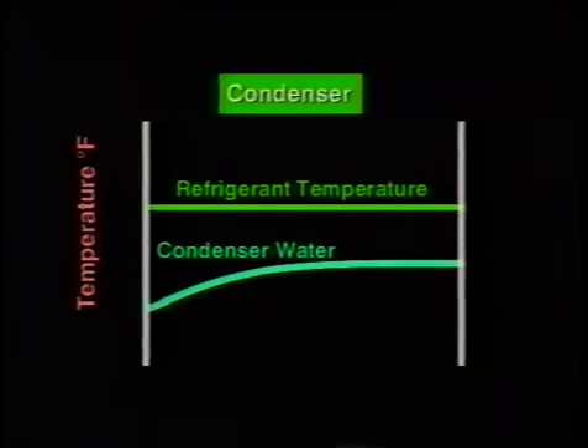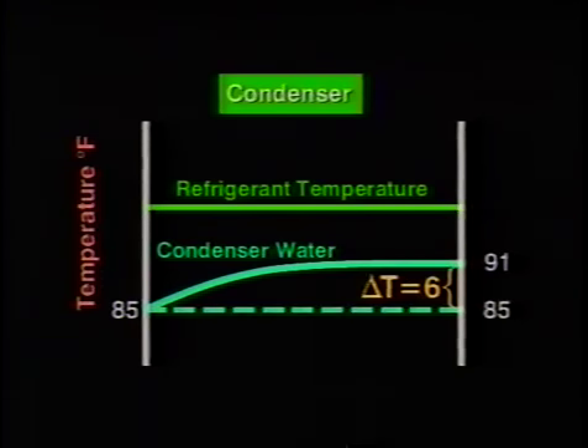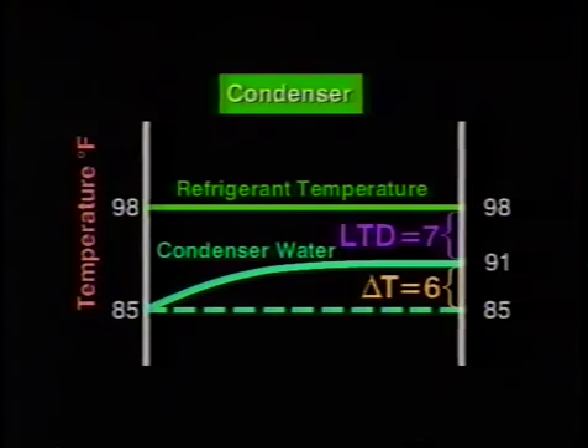Now we'll look at the condenser, where water is entering at a normal 85 degrees Fahrenheit and leaving at 91 degrees, giving us a delta T of only 6 degrees instead of the expected 10 degrees. Our condenser refrigerant pressure is 190 psig, giving a saturated condensing temperature of 98 degrees instead of the expected 104 degrees. From the approach curve, we see the LTD is low at only 7 degrees Fahrenheit.